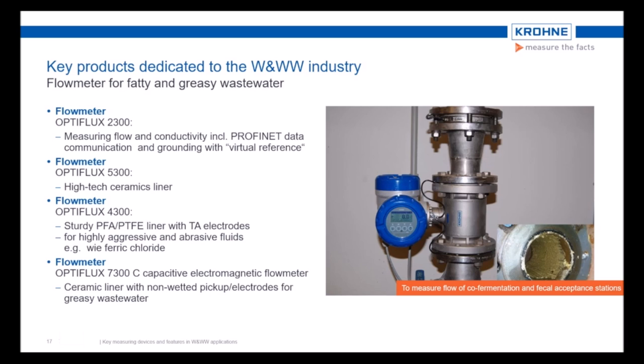Due to the special capacitive electrodes which are installed behind the liner, this device has no direct contact to the media, and therefore the performance and stability of that meter is independent of the content of fat or grease. The sturdy ceramic liner also guarantees stable measuring under harsh conditions. So this flow meter is dedicated for use in fecal acceptance stations or at the inlet of a co-fermentation station.